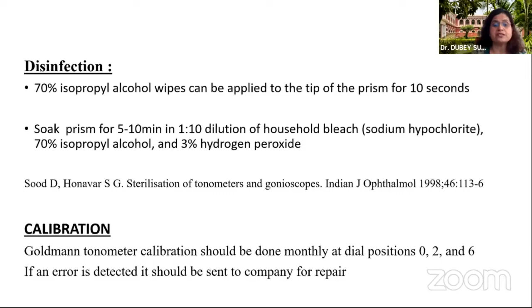High level disinfection is achieved by soaking the prisms for 5 to 10 minutes in 1:10 dilution of sodium hypochlorite or 3% hydrogen peroxide. Calibration should be done monthly, and if any error is detected, it should be sent to the company for repair. Perkins tonometer is an applanation tonometer, which is portable.